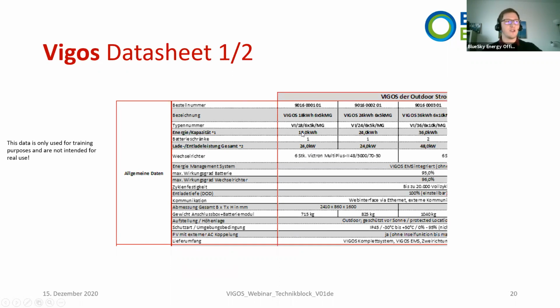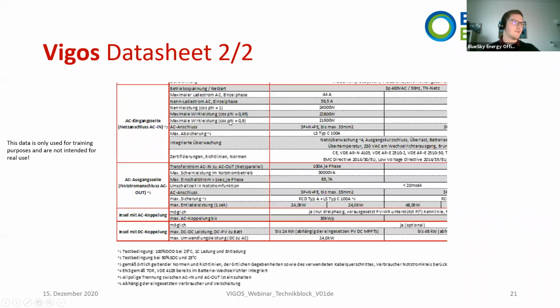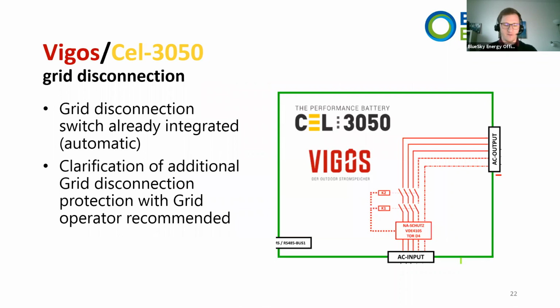In there you have all the needed information: the capacity, the power, which inverter is used, the weight, the size, and additional information. On the second part of the datasheet, you have a lot of power information. You see how it should be fused, what the maximum reactive power needed is, and such stuff. What's the maximum AC coupled island PV you can add, and what's the maximum DC coupling which is available right now. So please just take a few views into the datasheet so that you are aware of all the data. If the datasheet is a bit too complicated written, please just give us a call and we try to explain it to you, or just write us an email at support@bluesky-energy.eu.